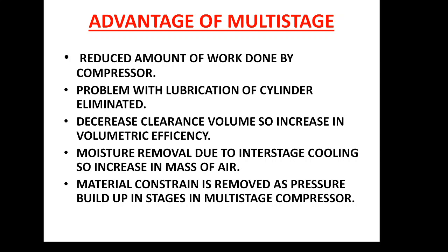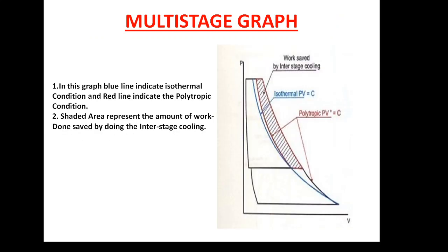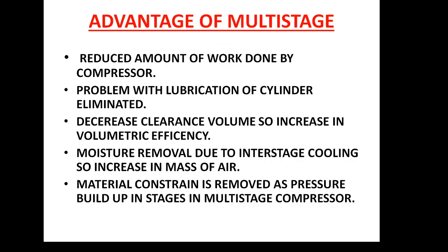The third advantage is that by doing compression in a staged manner, we are cooling the gas in between stages — this is called intercooling — which improves volumetric efficiency. Volumetric efficiency is increased because as we cool the gas we remove moisture, and we also decrease the volume of gas while increasing the mass of air. As the mass of air increases and volume reduces, volumetric efficiency increases.